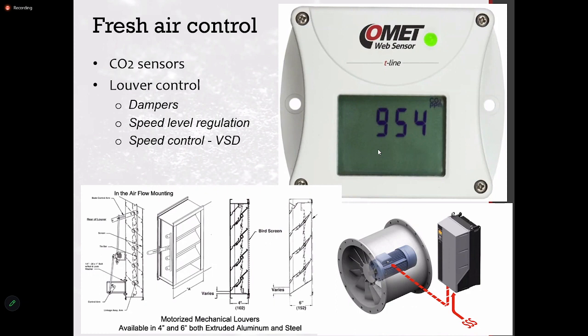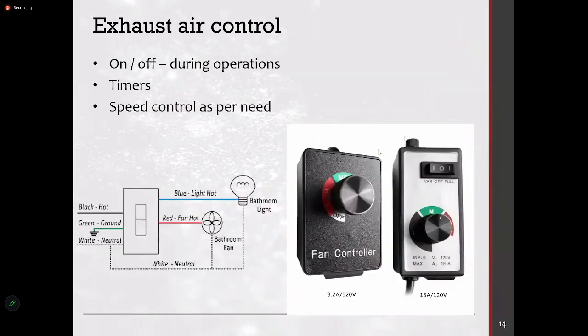So if you think VSD is very costly, you can also do the speed level regulation where you have about 2 or 3 speeds. So that is also quite worthwhile. Then you have a simple contactor system and you instruct the controller to which level the speed should be increased. That is very much effective, just like a fan control. You have maybe 3 speeds or 5 speeds sometimes, to have the correct level of air supply, so you are not giving more fresh air or you are not compensating on the CO2 levels. Yeah, so these are speed control.